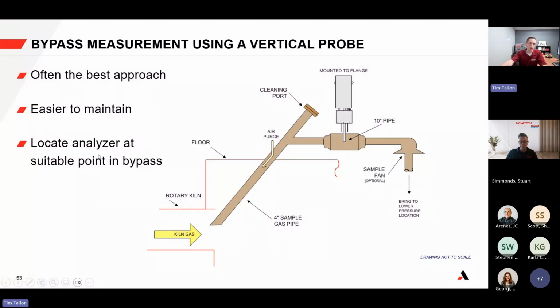There are different ways to bypass the measurement. With a vertical probe, if there's a kiln, you could have a separate tube that draws a sample. What's drawing the sample? There's an induced draft fan downstream that pulls the sample, giving the analyzer access to make the measurement in a separate space without being right in the middle of the high particulate. That's an example with a vertical probe.